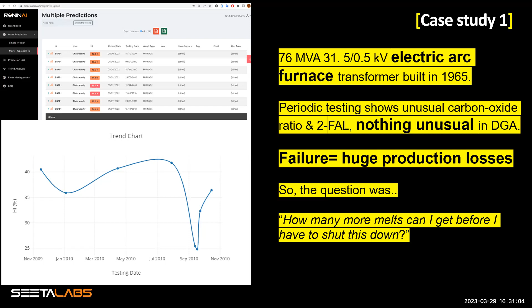And given the current status, which was about 25% at that point in time, it was alarming, really alarming. We decided that they should halt the operation for a certain period and do a visual inspection of the asset. Upon visual inspection, it was identified that there was a gasket leak, which was causing ambient moisture to ingress inside the transformer, thereby increasing the moisture of the oil inside and showing all kinds of anomalies.